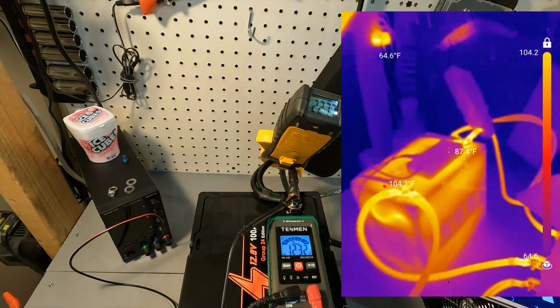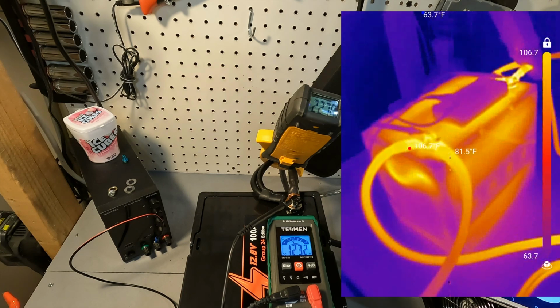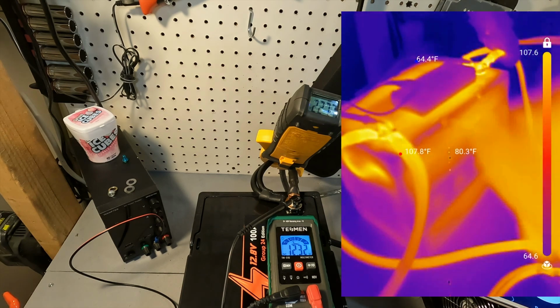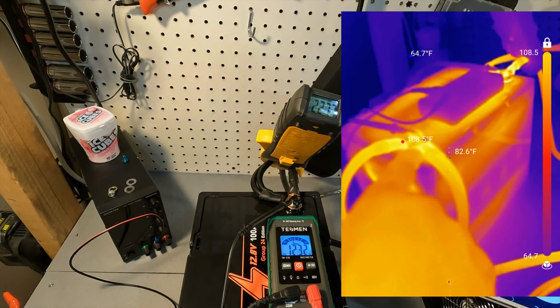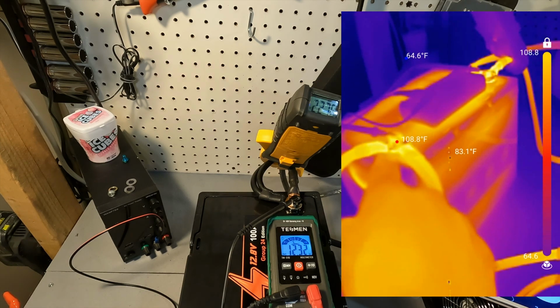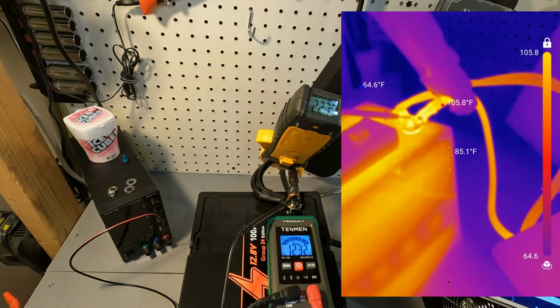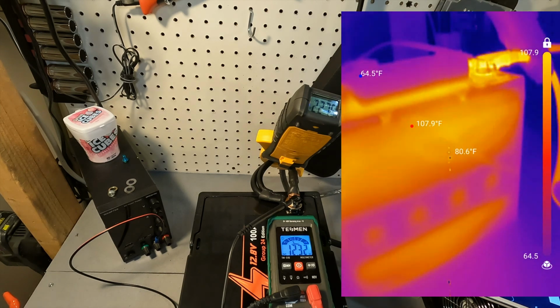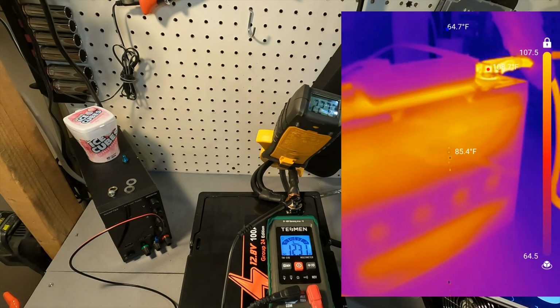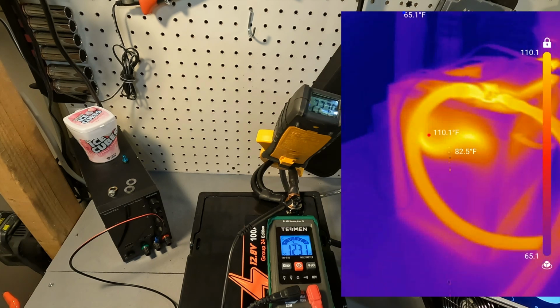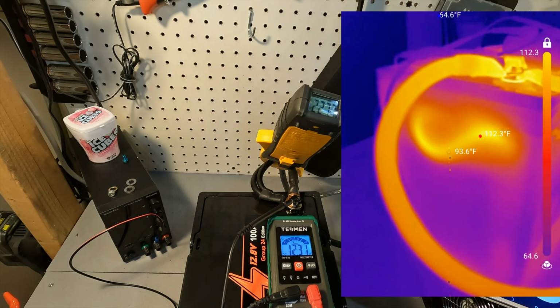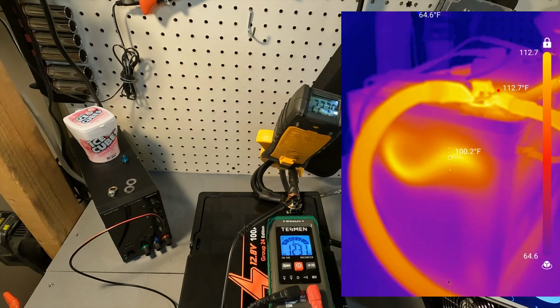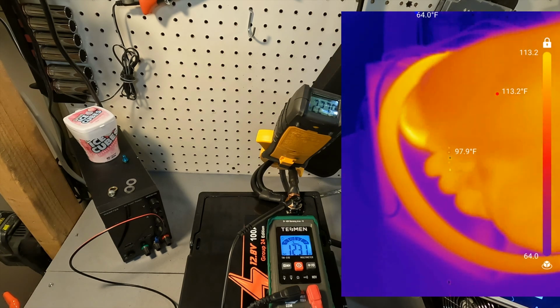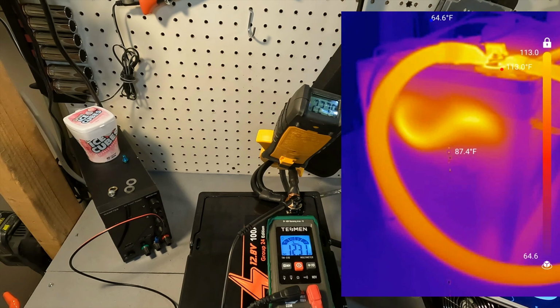Okay, let's look at the thermal for this battery. You can see right here, we're looking at 108 degrees Fahrenheit, which isn't terrible. 107 over here. The sides of the battery are still at 85 degrees. You can see that wire inside — it's at 112 degrees right there. 110, so it's getting real hot, and that's on the outside of this case. So you got to wonder how hot that wire is getting.